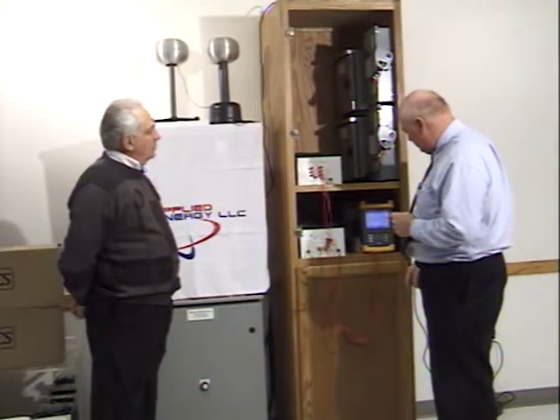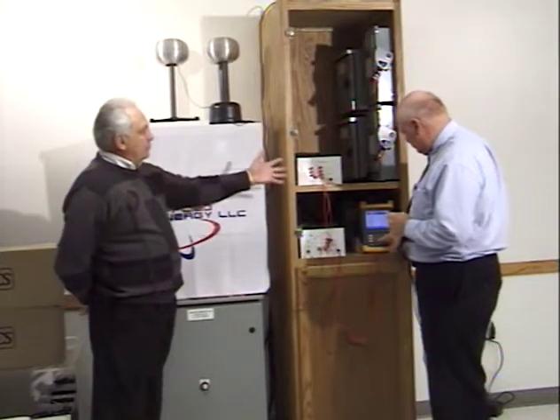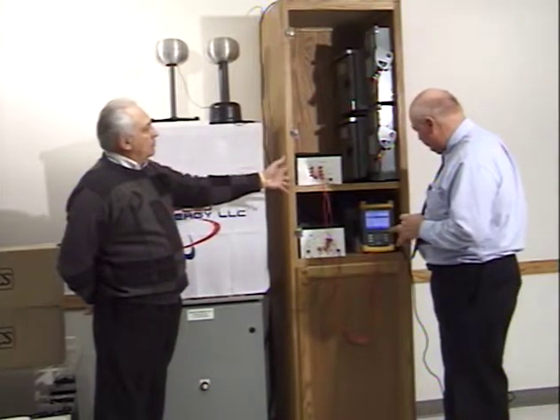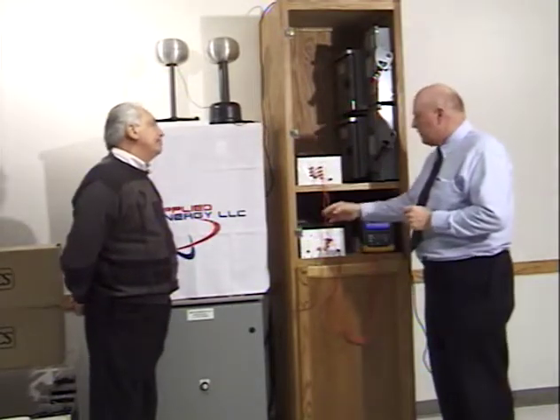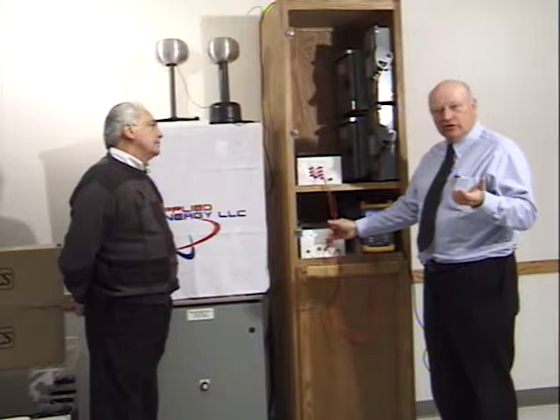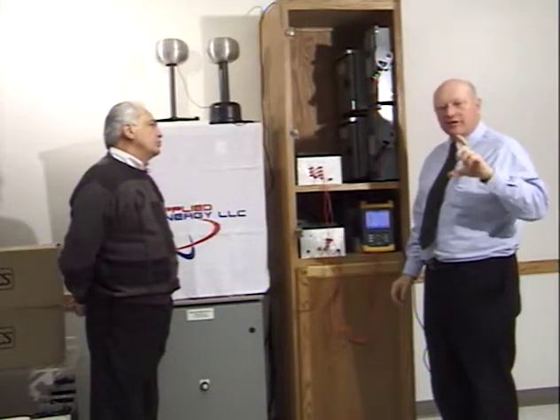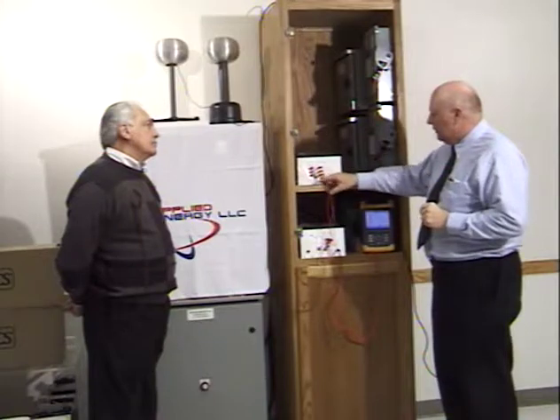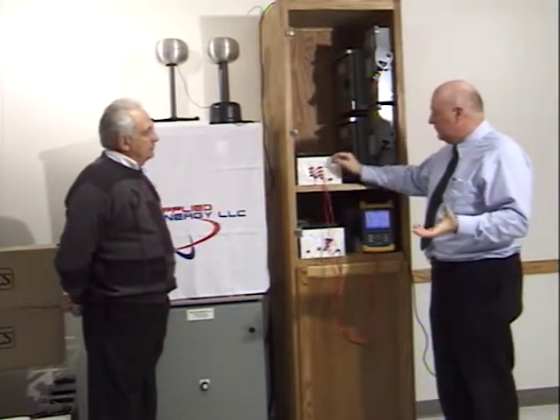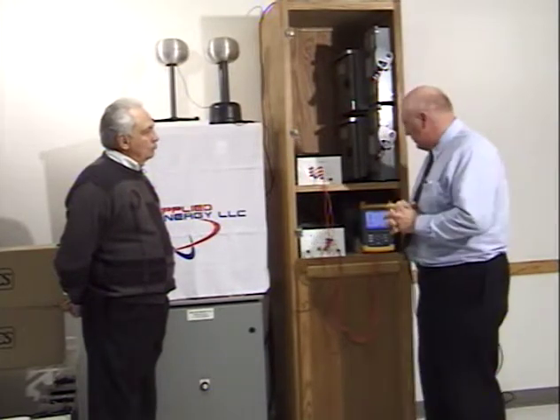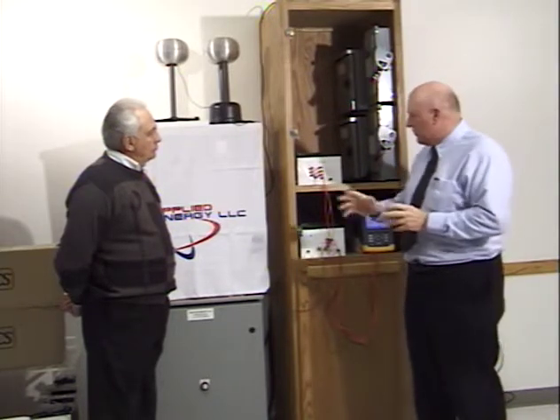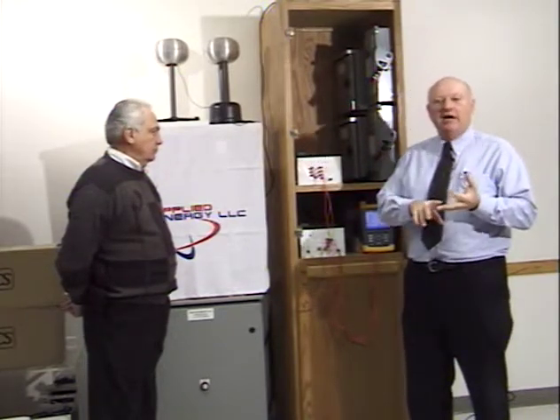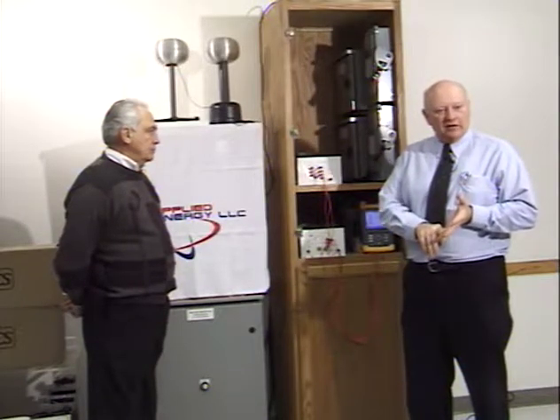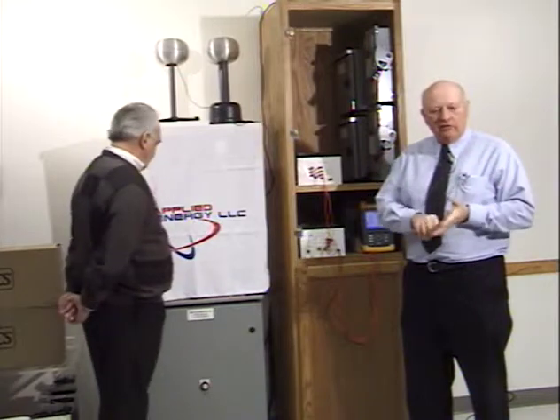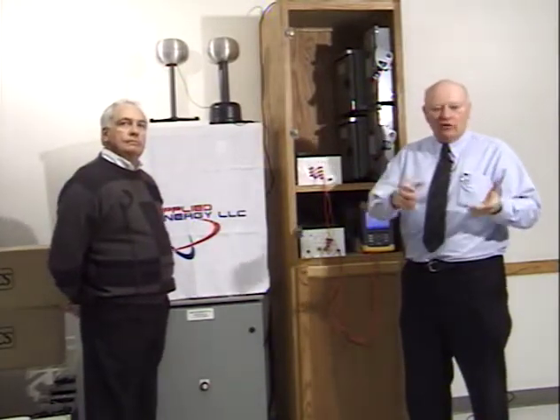Now, before you turn that on, Bill, again, what if any types of problems will occur between that drive and motor if you don't have this type of protection? Okay, what does happen, you have high voltage spikes that can be 2 or more times system voltage. That will deteriorate the insulation in the motor windings. You also have a high harmonic content. As we see when we power up here, the adjustable frequency drives will typically generate a high amount of 5th harmonic and 7th harmonic. Harmonics are like octaves in an audio, in a piano or guitar or something.